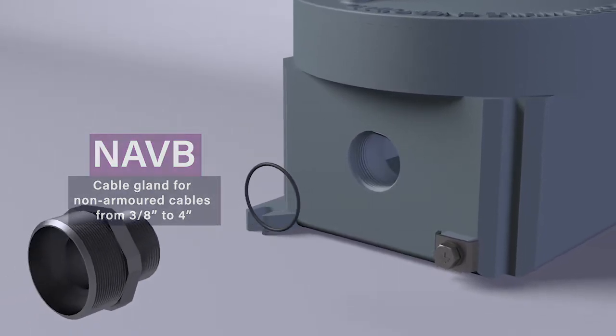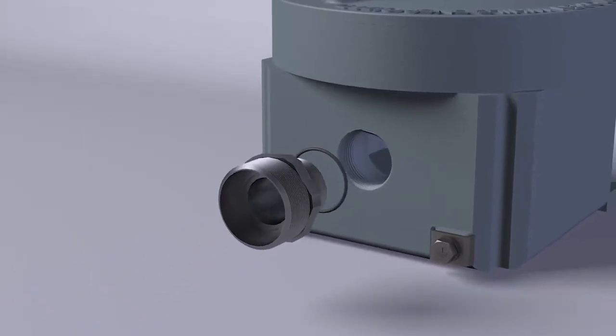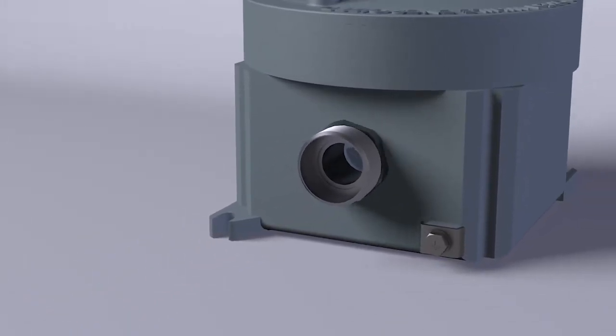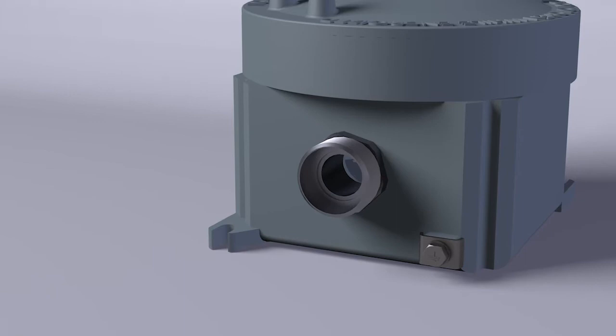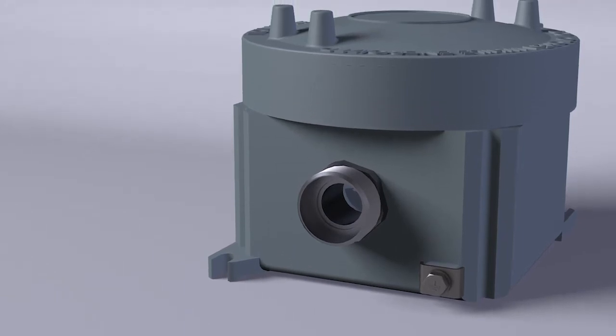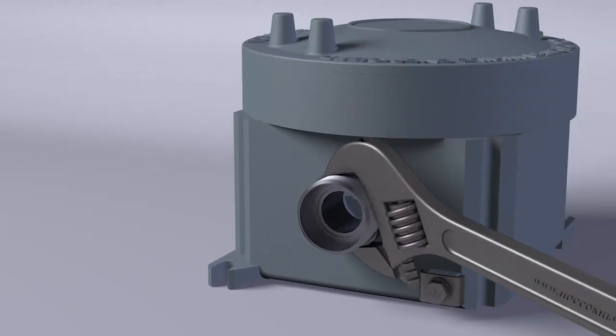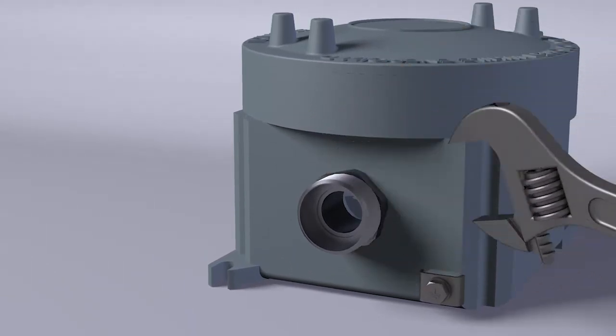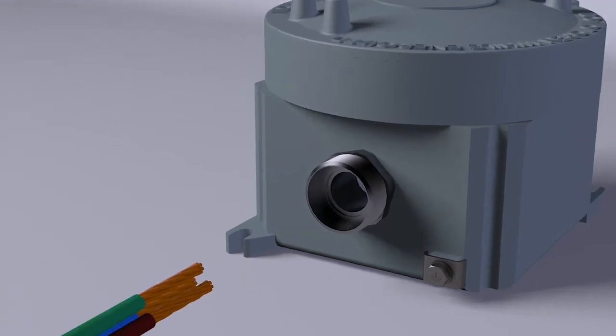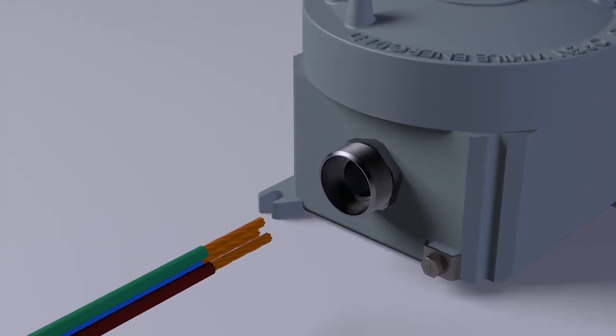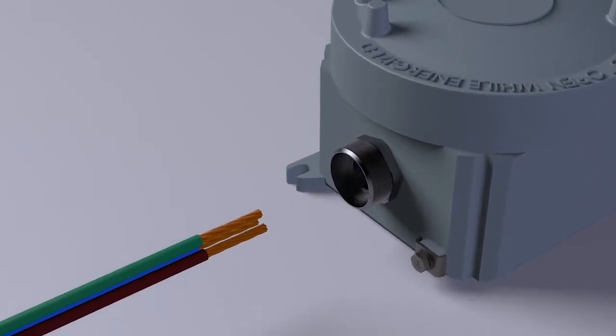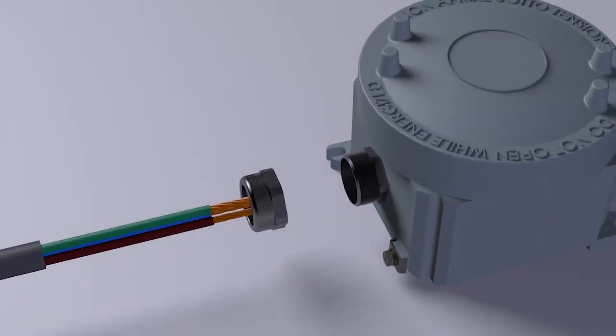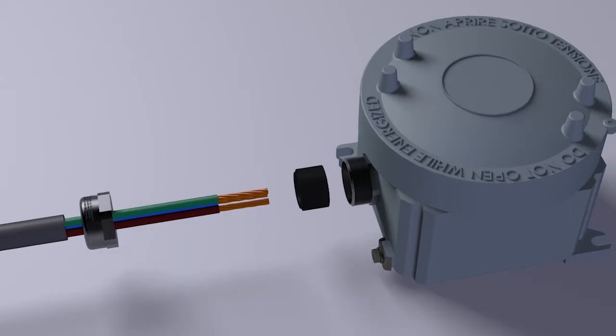Screw and tighten the cable gland including the gasket (in the case of ISO metric threads) into the enclosure or into the equipment. Insert the nut and the ring nut, locking them to the cable if necessary with adhesive tape so as not to hinder the sealing phase.